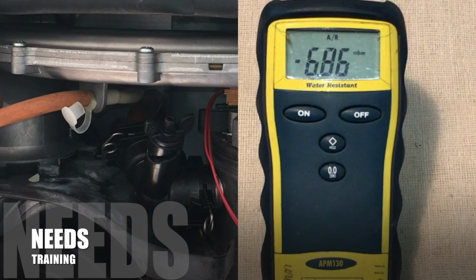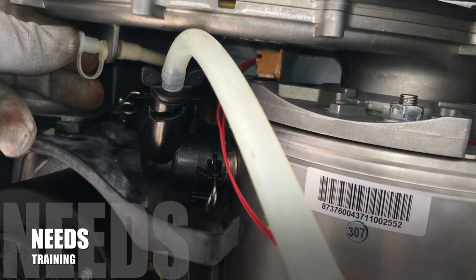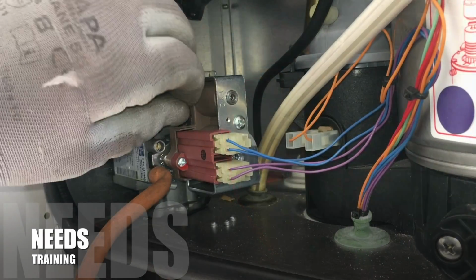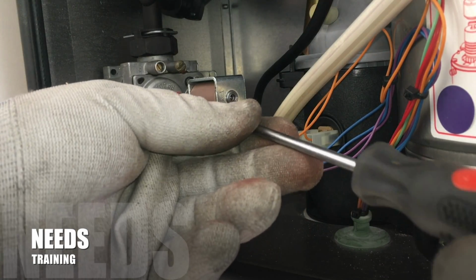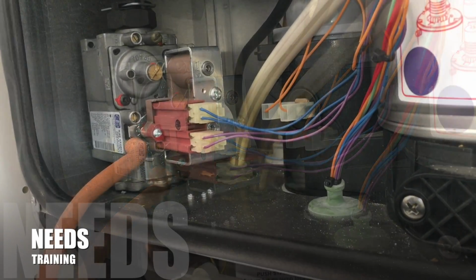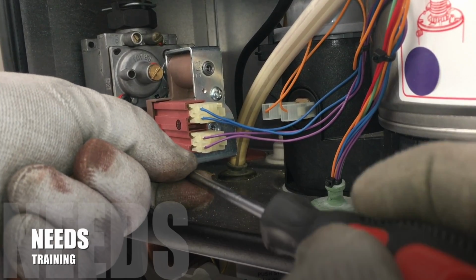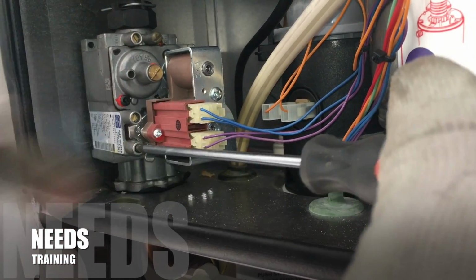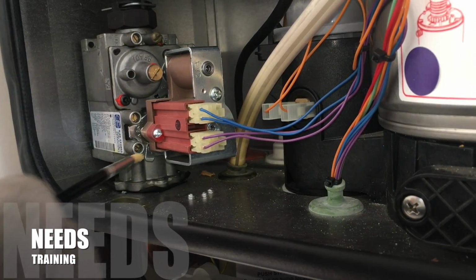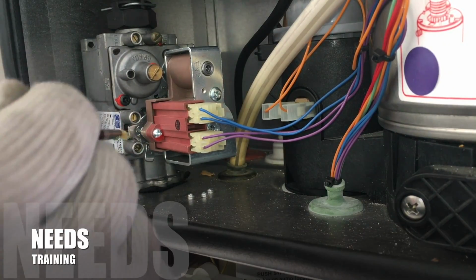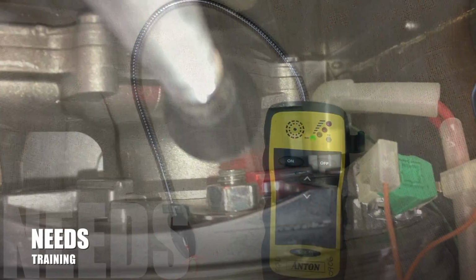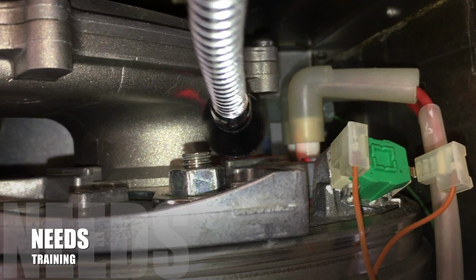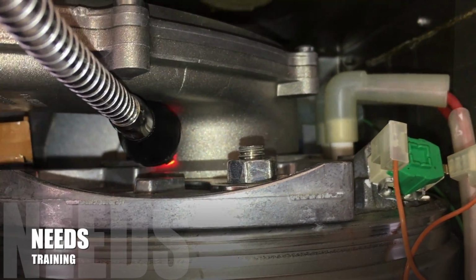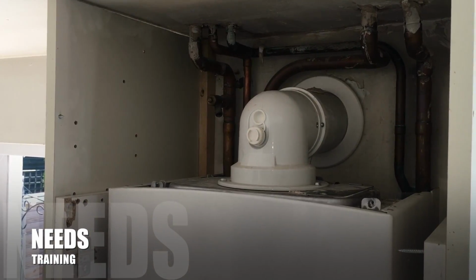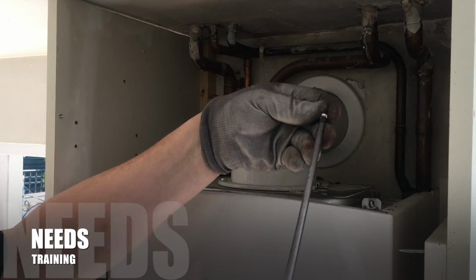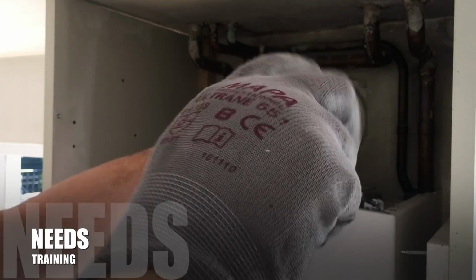A final fan pressure test. Replace test point cap. Using leak detection fluid, make sure you haven't left any leaks. With the gas detection unit, check the burner seal. Replace the cover on the appliance.